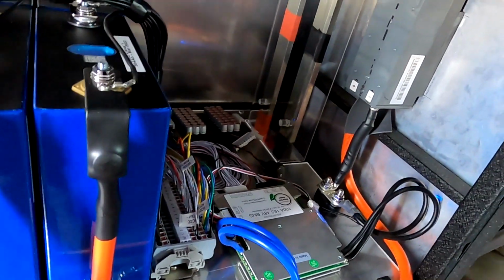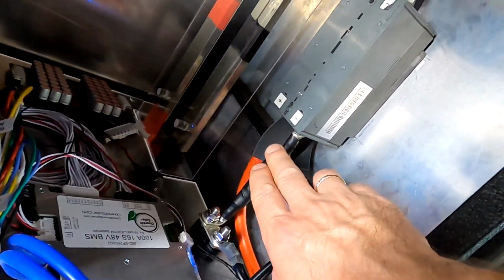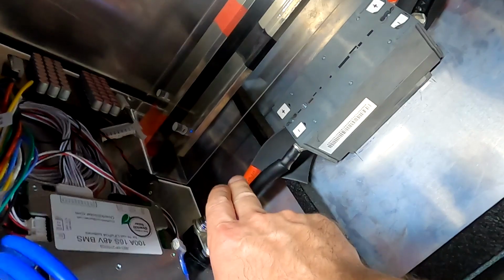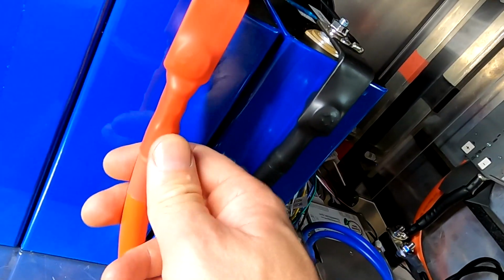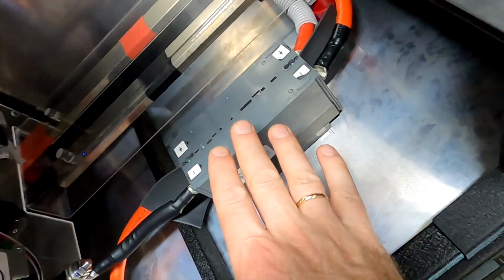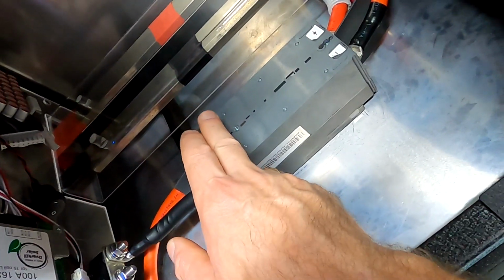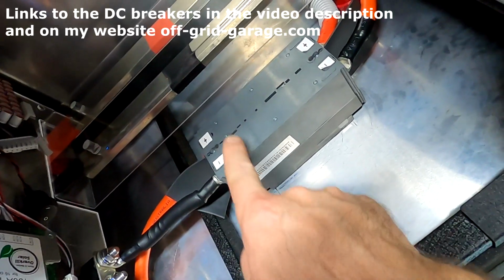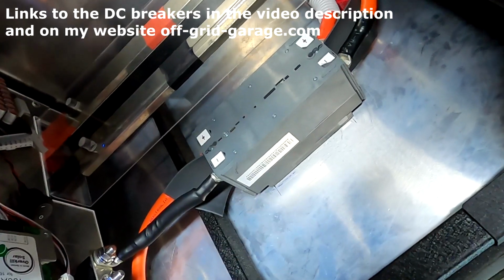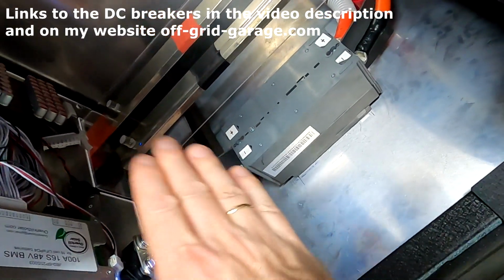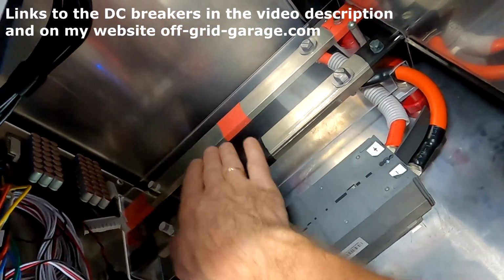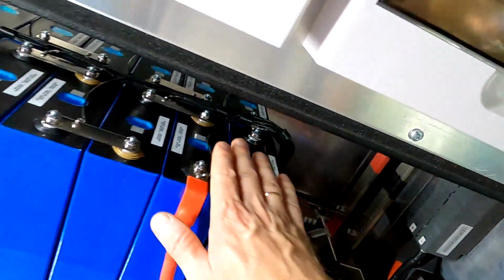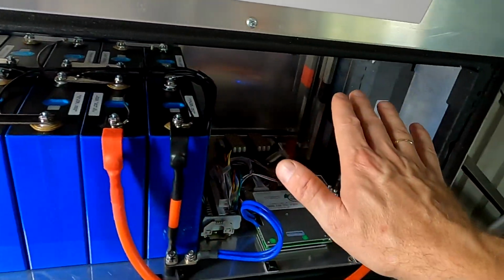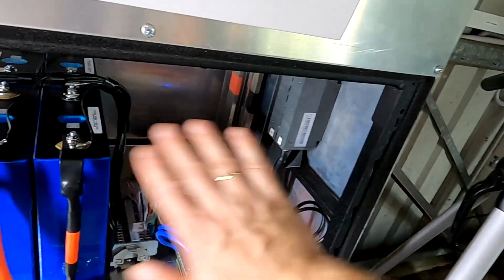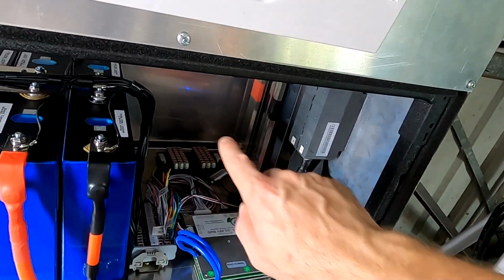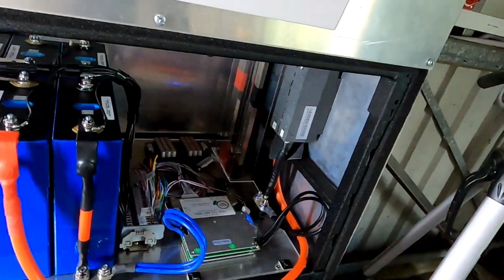A lot of people have asked under my videos if you have to fuse your negative and your positive at the same time of the battery. Usually you only fuse the positive, but I like to isolate my battery completely, positive and negative. That's why I have a 2-pole breaker in here, so negative and positive gets completely disconnected from the main bus bar system, and I can work safely on this battery without having to fear anything. It is completely disconnected, isolated from the system.